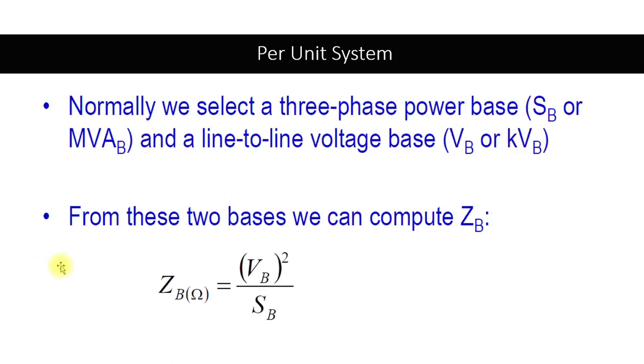Normally we select three-phase base power and line-to-line voltage as our two chosen base quantities. The remaining two — impedance and current — are calculated from these. Since Z equals V squared divided by S, we get Z base equal to V base squared divided by S base.